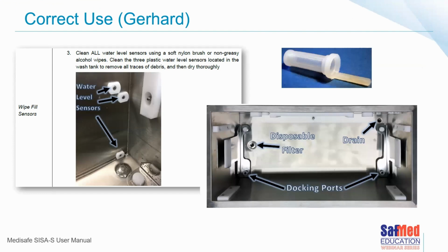On this picture, you can see on the left the white sensors. The top one is your overflow sensor. The one just below is your normal water level. And the one right at the bottom of the chamber is your minimum or drainage water level. So in the case where, as Xana has mentioned before, your machine is not 100% level, you will find that you've got water in the bottom of the machine, and the bottom sensor is still picking up that there is water, so the machine will just keep on draining. And you cannot stop it because the water is still activating the sensor.